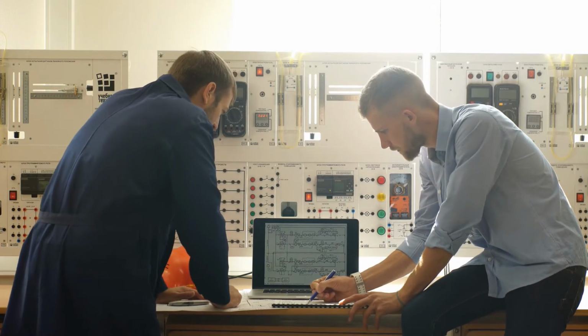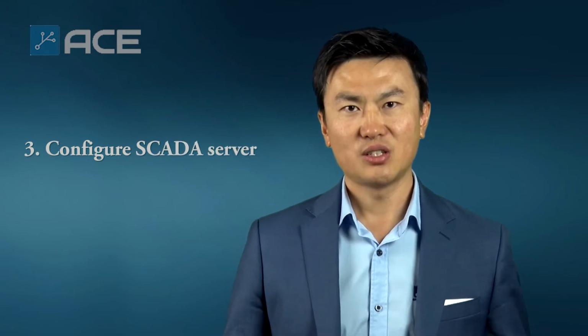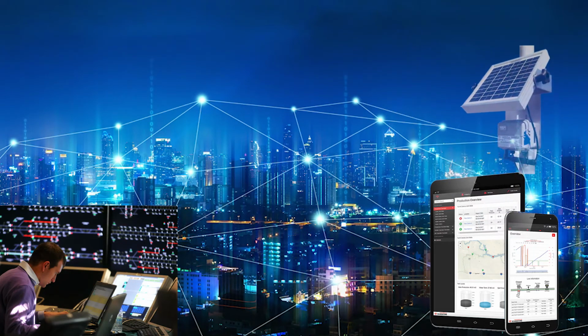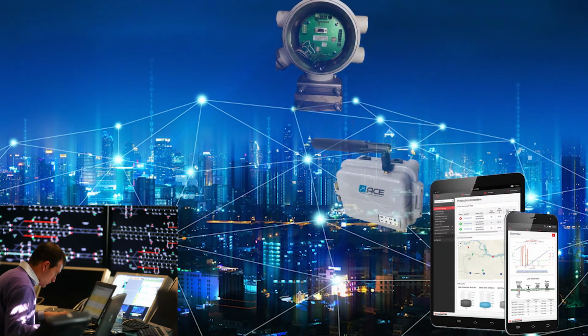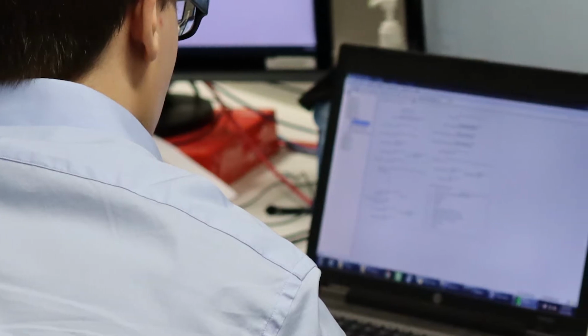control and monitor. The second benefit is that it has different alarm classes and event classes, which help clients to classify and filter the data in whichever way they want. The third benefit is that clients are able to configure the SCADA server to remotely download the configuration to the field devices. This provides such a useful benefit to clients to restore the field device configuration to a default level should anything happen to the site.